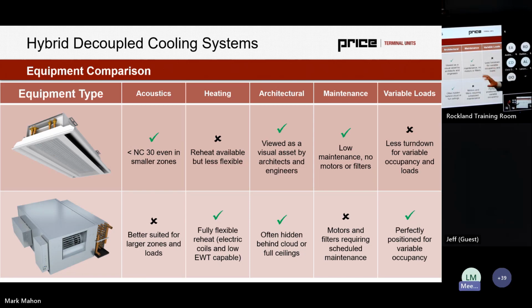The chilled beam is generally lower maintenance without its motors and filters, and then variable loads because of this equipment, which can handle up to 36 MBH all the way down to very low MBHs. That makes it really well positioned for variable occupancy. So two great tools in the tool belt. I like to think of it as a large Phillips head and a small Phillips head screwdriver. Both do the same job.